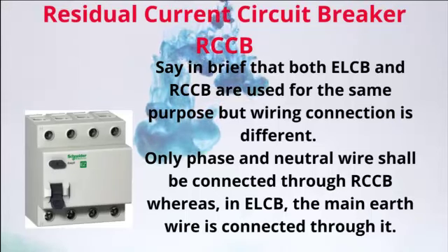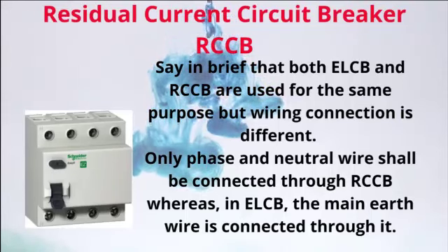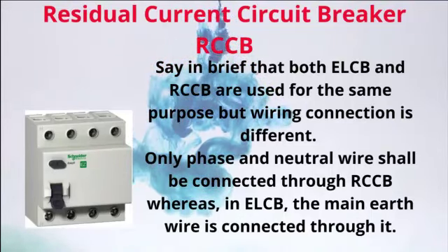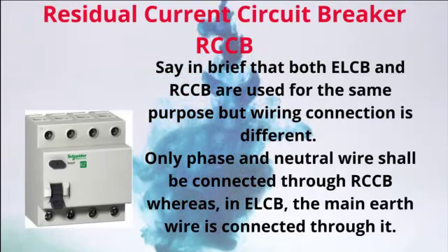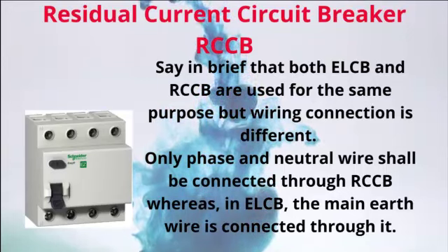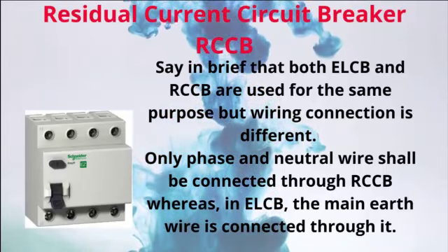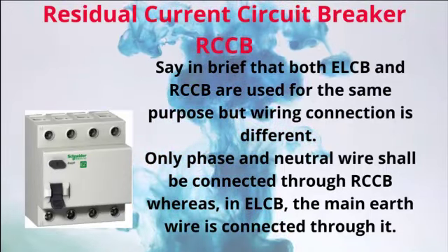To say in brief, both ELCB and RCCB are used for the same purpose but the wiring connection is different. Only phase and neutral wire shall be connected through RCCB whereas, in ELCB, the main earth wire is connected through it.